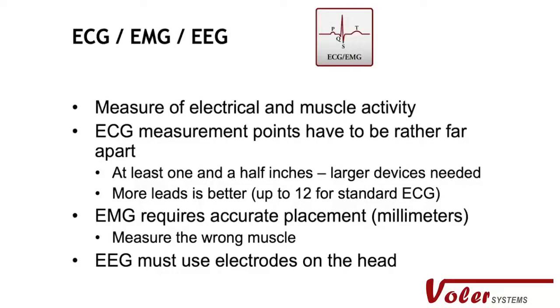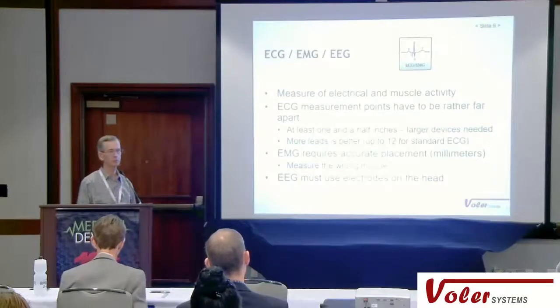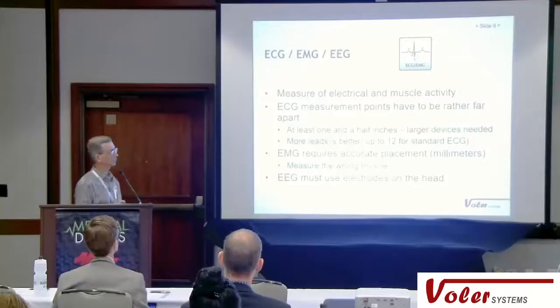ECG for the heart, EMG for muscles, and EEG for the brain all measure electrical signals. They all need electrodes, and people would like dry electrodes — getting a wet electrode and applying it with a wearable device is inconvenient. For ECG, it's important to have separation. On the chest, one and a half inches works. If you look at the Apple Watch, they're measuring ECG on the wrist, but what you may not have noticed is you have to reach over with the other hand and touch the watch — so they're actually getting from one hand to the other, far apart.